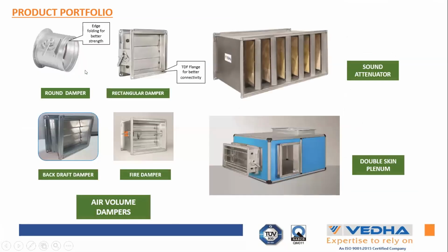Going to the next slide, these are the dampers. In dampers also there are several shapes, round and rectangular. Each product has a unique feature. In the round damper, we have edge folding for better strength. In the rectangular damper, we have flanges for easy connectivity. And we even have a hybrid version where the body is GI and the blade is aluminum. The GI body is for better strength and rigidity. The aluminum aerofoil blade is for smoother airflow, better volume control and less pressure loss.